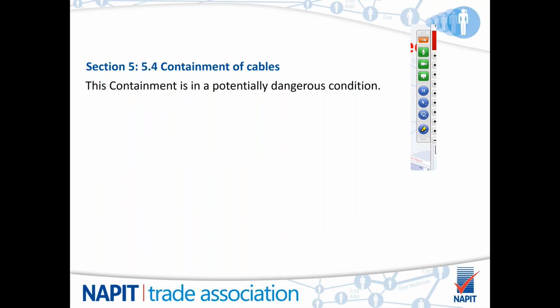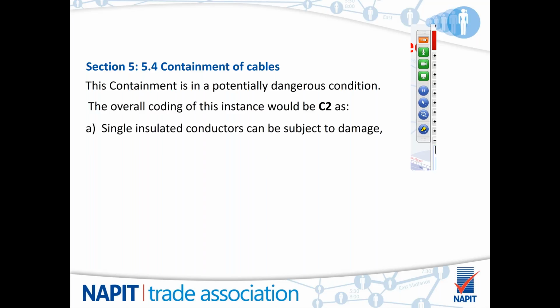Again, if we look at our inspection schedule under section 5, we've got containment of cables. And the containment is in a potentially dangerous condition. With everything all told, the overall coding will be a C2. We do have single insulated conductors which can be subject to damage. Again, this can be open to interpretation because it would depend on what could cause the damage and maybe how high the trunking is. But those conductors could definitely be damaged by something being inserted into the trunking.